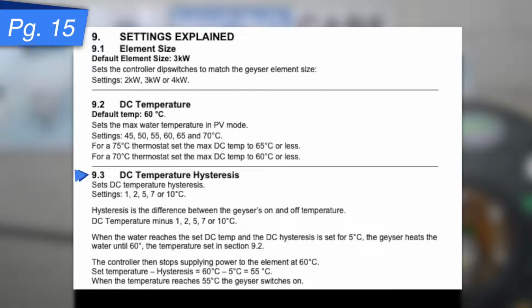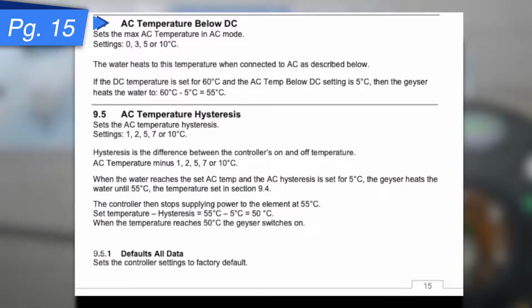The DC temperature hysteresis settings there are 1, 2, 5, 7 or 10 degrees. We would request that you set it as 10 degrees, which is the default from the factory side. The AC temperature below DC, normally we request again 10 degrees difference for that, but you can set it up as you want and as per what your client's requirements are.